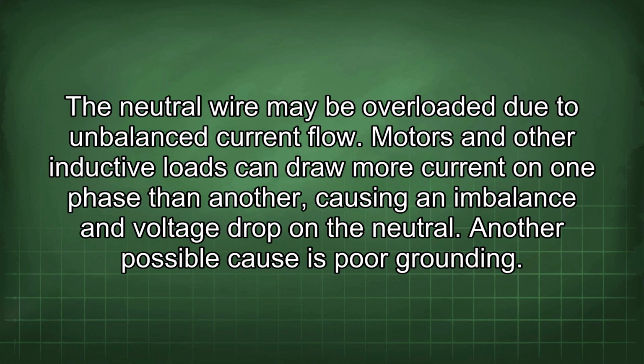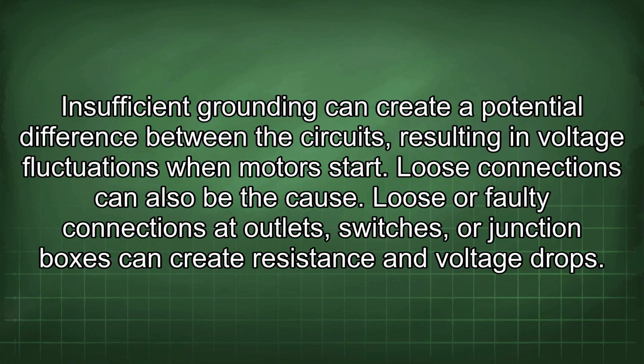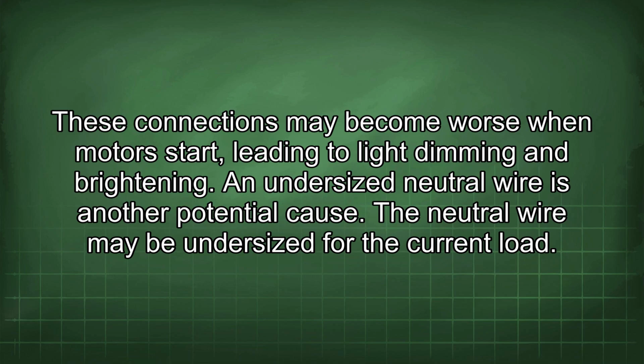Motors and other inductive loads can draw more current on one phase than another, causing an imbalance and voltage drop on the neutral. Another possible cause is poor grounding. Insufficient grounding can create a potential difference between the circuits, resulting in voltage fluctuations when motors start. Loose connections can also be the cause. Loose or faulty connections at outlets, switches, or junction boxes can create resistance and voltage drops. These connections may become worse when motors start, leading to light dimming and brightening.